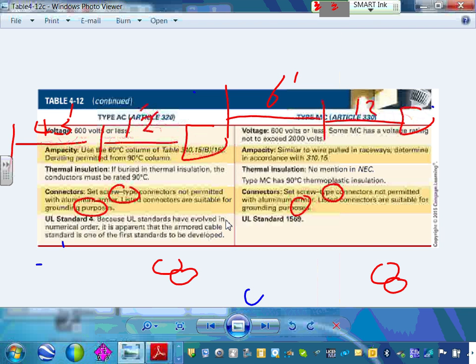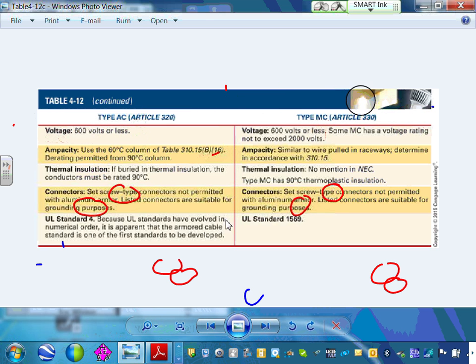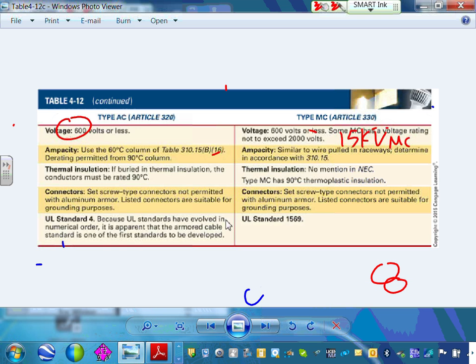Here's the last thing about this cable, and again, I'm emphasizing it, guys, because it's so important why our methods go through these. So voltages. Look at the superiority. Now another thing. Can you guys see the indication of voltage? MC cable can be 600 volts or less. Some MC cable has a voltage rating of 2,000 volts, but I know for a fact they can get 15 kV MC cable. So you can have a higher rating for MC cable. So you have 2,000, but you can even get it higher than that. 15 kV. So these you can get in higher voltages.